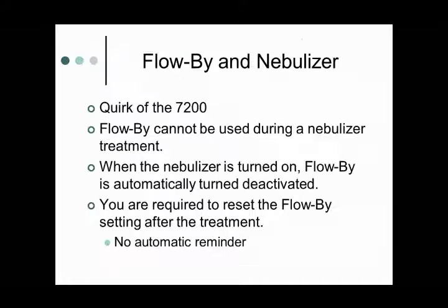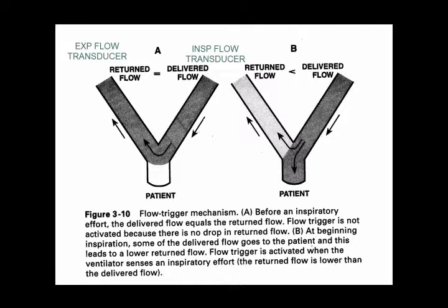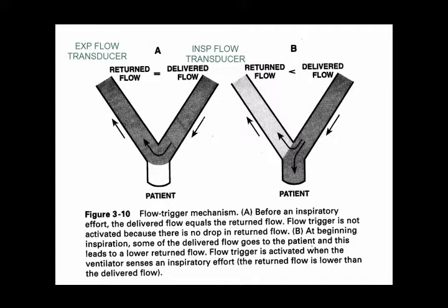Okay. Don't worry about this when this was talking about flow by in a nebulizer. Technically, when you would turn the nebulizer on, it automatically turned off flow by, but we're not going to talk about this. Go ahead. There's a way that I can teach you how to do it. Using graphics, I can determine how much leak I have, and I can set my flow sensitivity more insensitive to account for that leak. Yes, there is a way to do it.